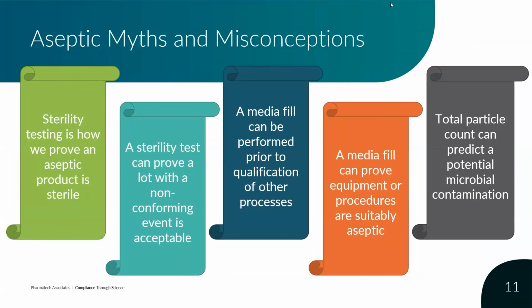The issue of why we focus on total particle counts is that we can do total particle counts in almost real time. We can have online monitoring, we can have online alarms, we can tell the operators immediately whether you've exceeded these particle counts, and then you can respond. And there is a general correlation that a higher level of particle counts is a greater risk of microbial contamination. It's not a perfect correlation, but the reason we depend on that is that we can't tell whether the microbial contamination is there until we see the microbial results, which unfortunately are several days later. They have to be collected and incubated on media in order to be detected. So that's why we depend on those total particle counts. That's why we evaluate those total particle counts in real time. And we're trying to predict in advance the potential risk of microbial contamination.